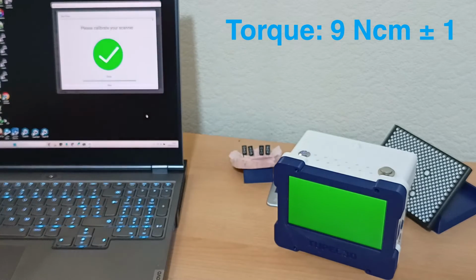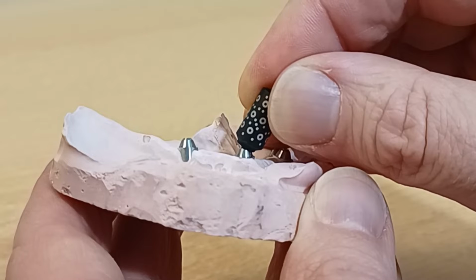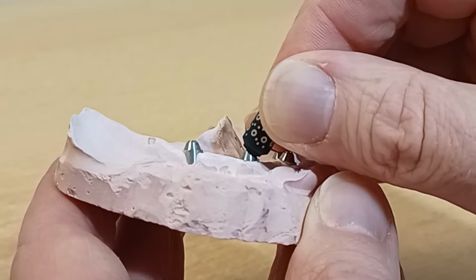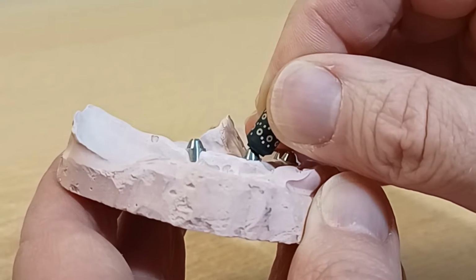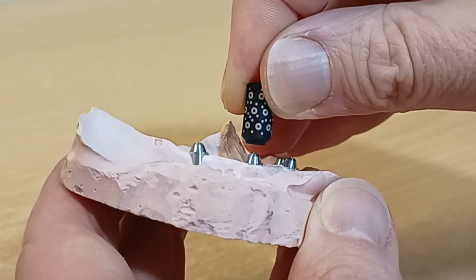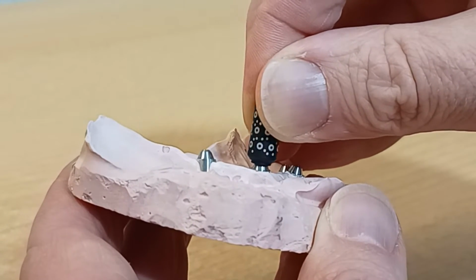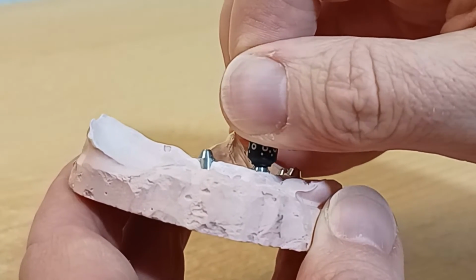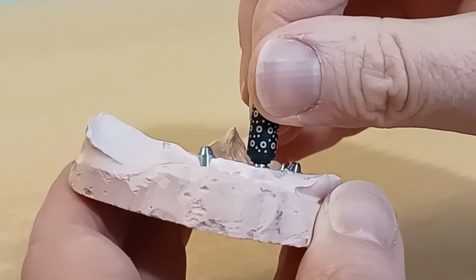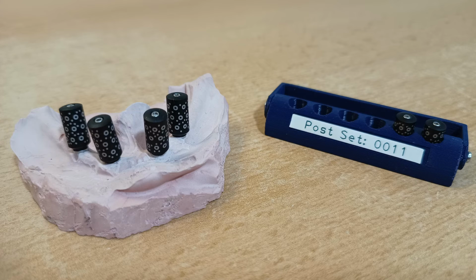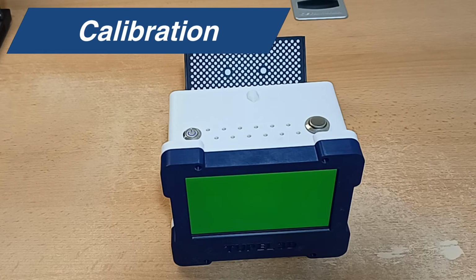Also, be sure not to screw the posts in at an angle. This is the wrong way. You could cross-thread the screw and cause abutment damage. This is the right way. You keep them straight as you screw them in. Each post has a unique dot pattern, so you can put any post in any position and the scanner will work out where they all are.